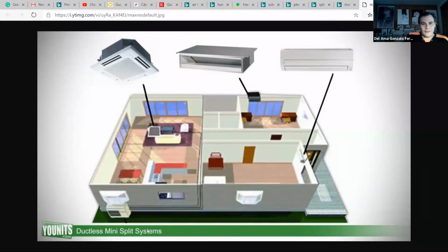Nowadays, all multi-split systems use this variable refrigerant flow, I think. But in buildings more than 10 years old, we can find multi-split systems that are not variable refrigerant volume. That means if only one of these units is on, the heat pump is still working at full capacity - it can't adapt electricity consumption to demand. So if I've dimensioned the system for three units but I'm only using one, without variable refrigerant volume the heat pump consumes a lot of unnecessary energy.